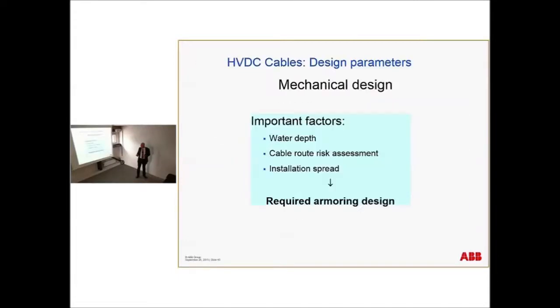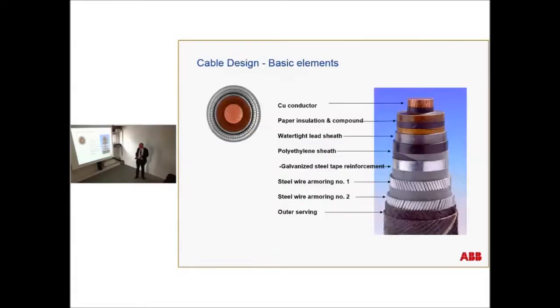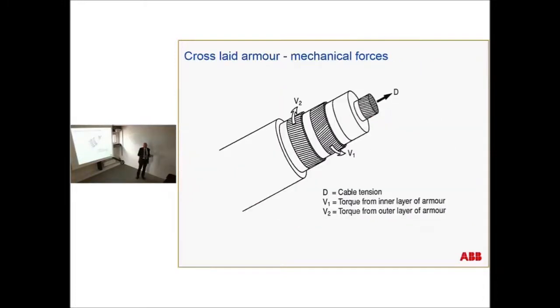Another thing is, if you have a lot of fishing activities or other submarine activities, then you might need to reinforce the cable. Also, how you install the cable, how easily you can bury it on the seafloor, and how deep you can bury it. Here, as you can see, again the same cable. Here you can see that we have two armoring layers, and they are oriented in two directions, so the torque should be neutralized by the inner and outer layer of the cable.